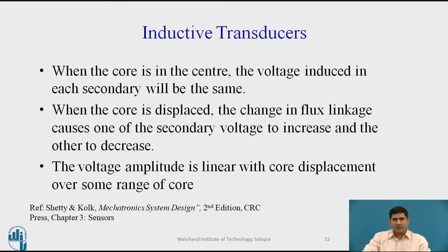When the LVDT core is at the center, the voltage induced in each secondary will be the same. When the core is displaced, there is a change in flux linkage, which causes one of the secondary voltages to increase and the other to decrease. The voltage amplitude is linear with core displacement over some range of the core, and this is typically where the measurement will be done. If you intend to measure in the nonlinear range, then corresponding signal conditioning circuitry will be required.